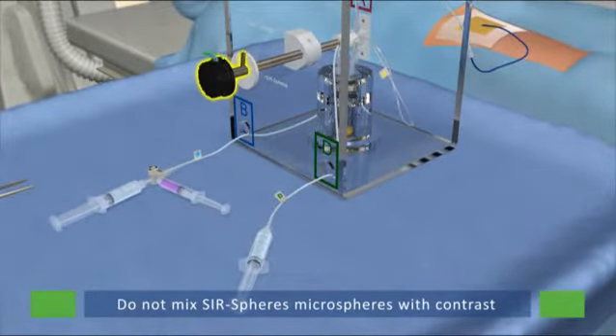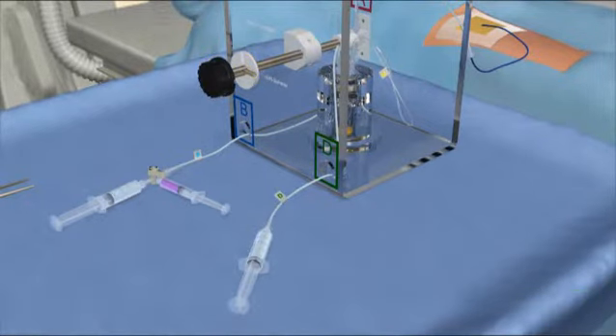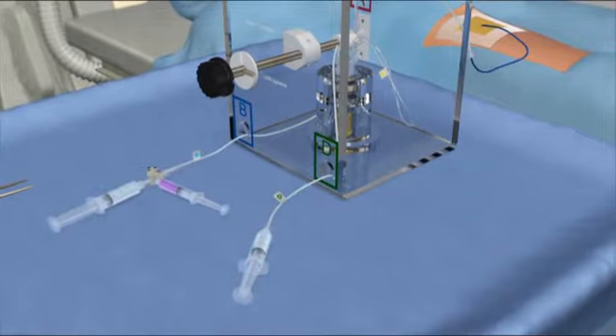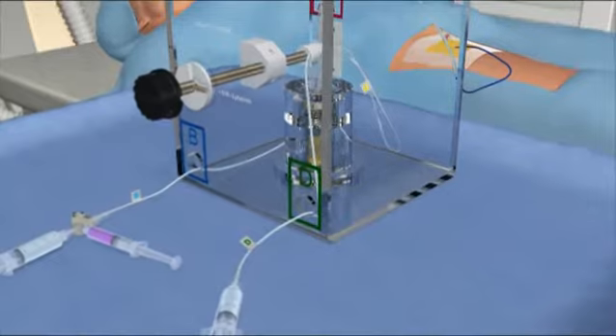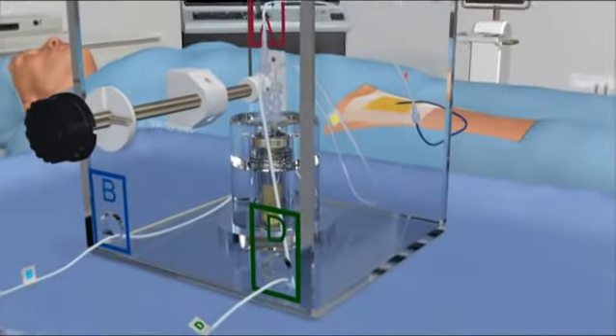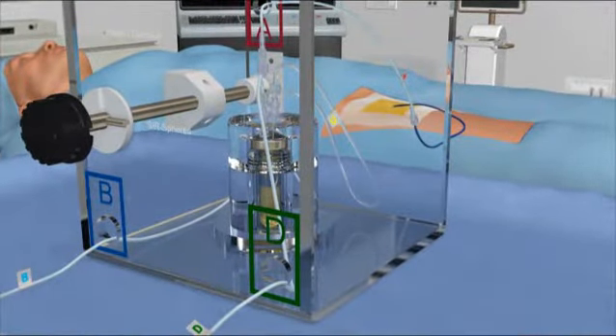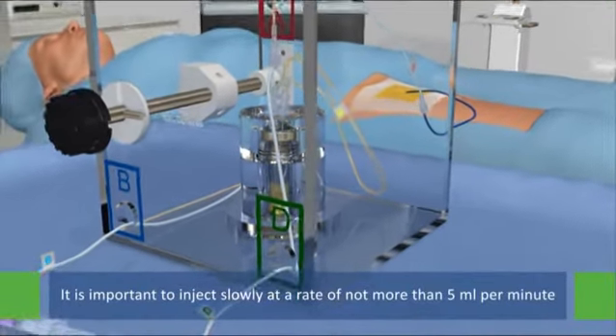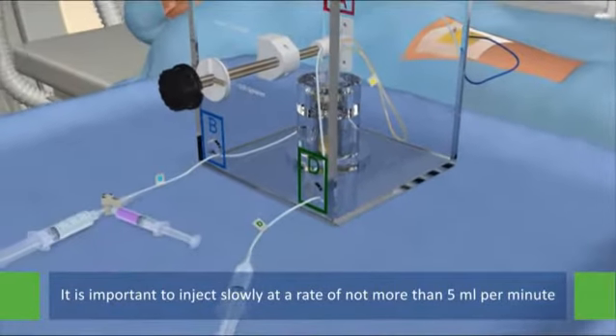Turn the black stopcock control knob to the 3 o'clock position, which is the on position to the microspheres. Now, inject water for injection from the 20 milliliter syringe connected to the D line in pulses of 0.25 to 0.5 milliliters, separated by a pause. This will cause the Sirtex microspheres to swirl into suspension, passing through the C needle via the C line into the A line, which is connected to the catheter. It is important to inject slowly at a rate of not more than 5 milliliters per minute.